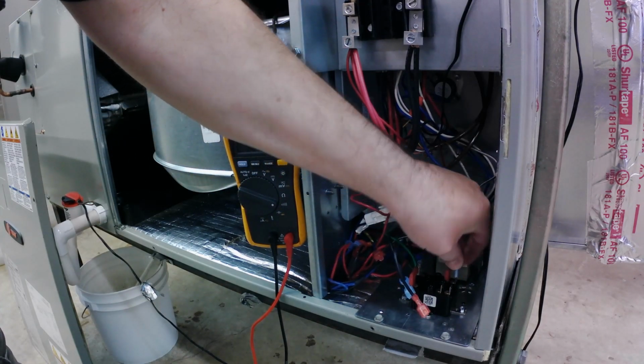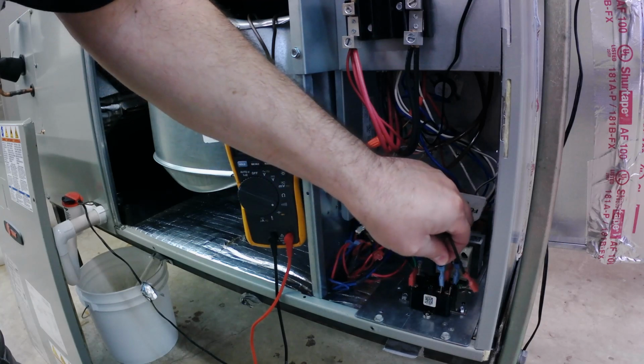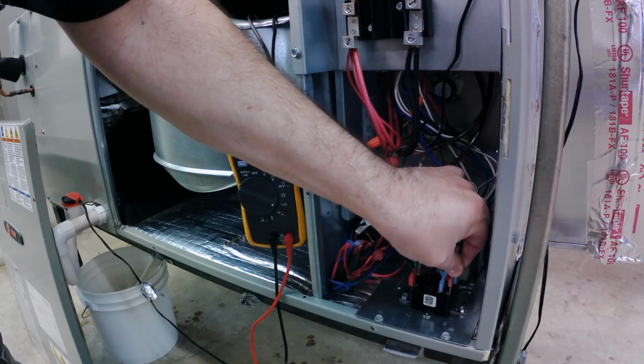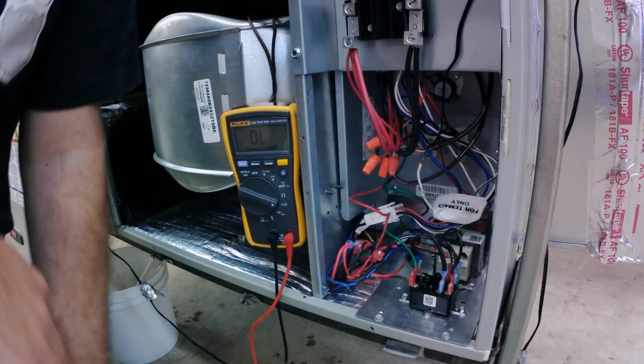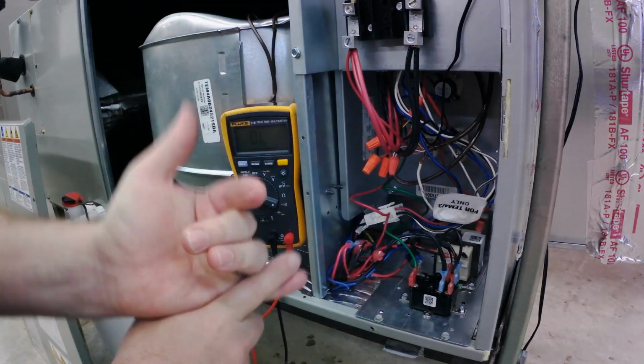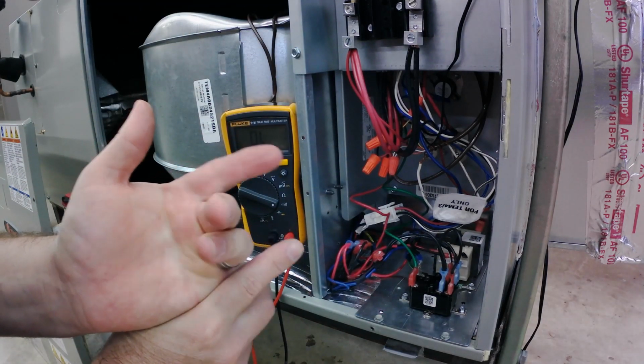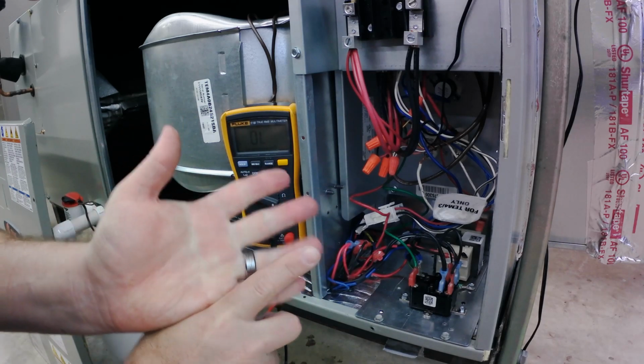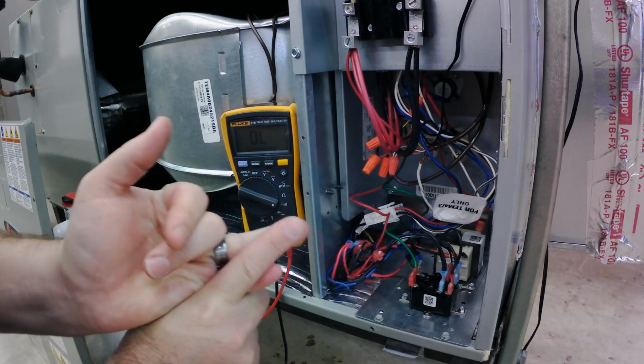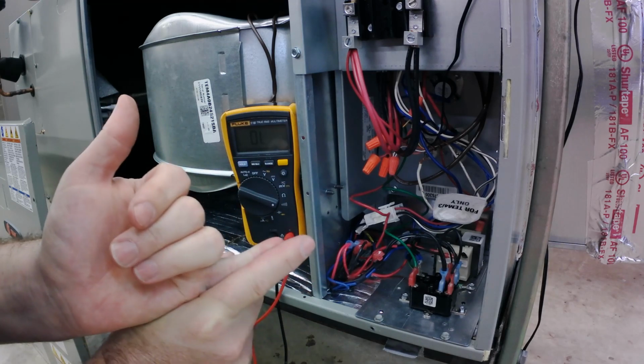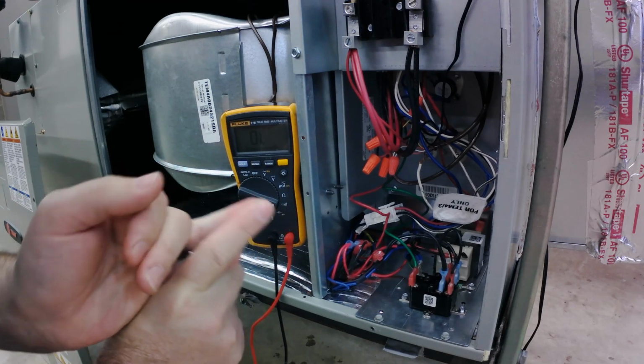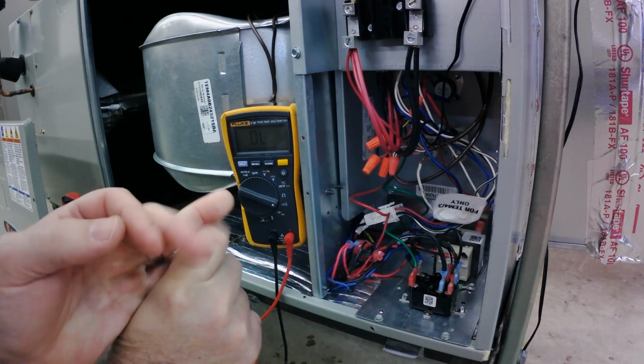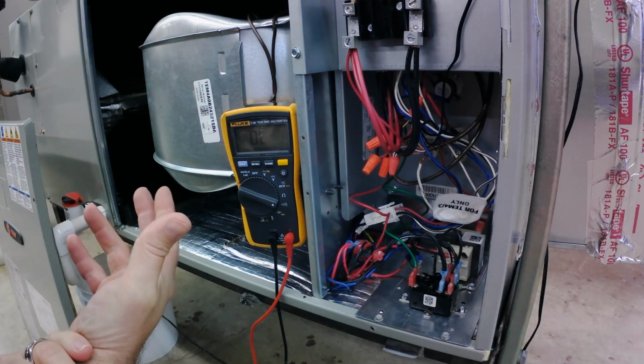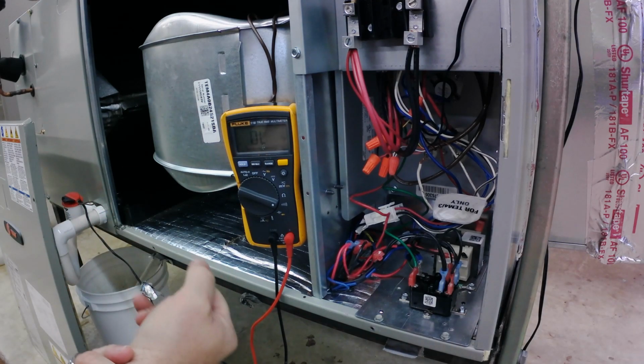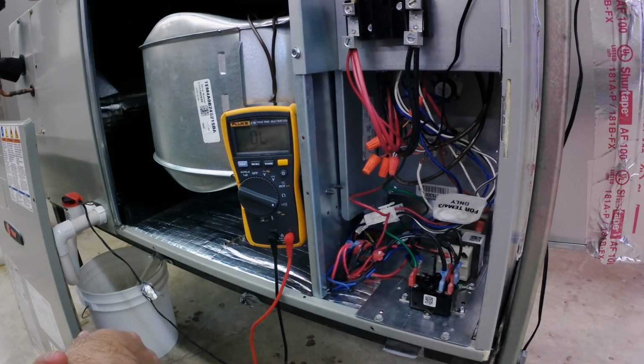Well, that's about it. Hopefully you understand a little bit about the relays and the contactors. Between diagnosing the thermostat properly and knowing how to troubleshoot it a little bit, and diagnosing a relay, making sure that you check the coil and the switches separately and together, you'll get a little bit better at properly diagnosing bad motors, bad capacitors, bad relays and bad thermostats. So until next time, I'm out of here.